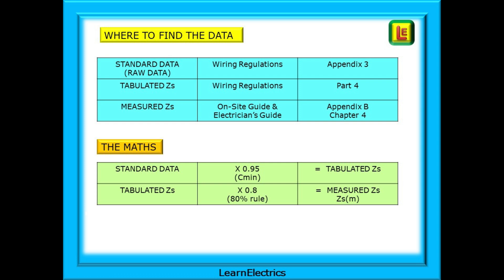Measured ZS is found in the on-site guide. And this is the ZS that you will measure and check against with your test meter when on-site. The maths part reminds you of how to get the numbers, when to use Cmin, when to use the 80% rule. Measured ZS is sometimes written as ZSM with a small m in brackets, just to show that this is the measured ZS value.